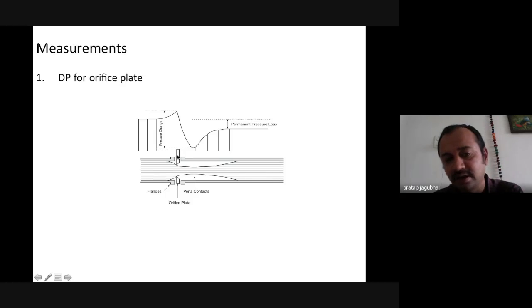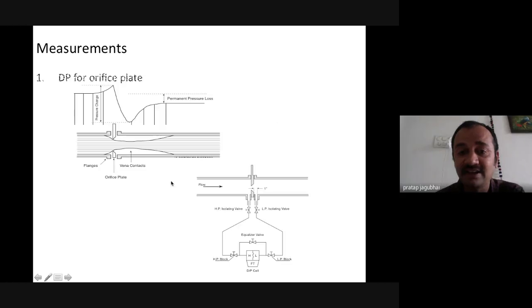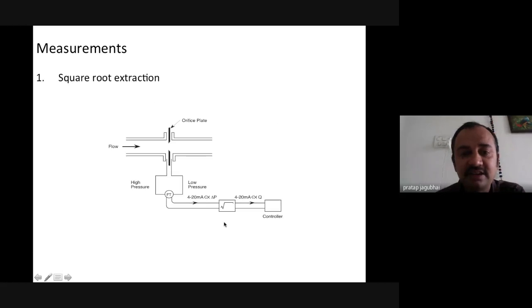In the DP type measurement, the orifice plate is inserted inside the flowing media, where you can see that when the orifice plate is available, there will be a pressure difference, and the lowest point of the pressure, which is getting dropped, is called the vena contracta point, and we take the pressure difference from this point to this point, which is a differential pressure equivalent to the flow. And this is very well defined from Bernoulli's equation, where flow is proportional to the square root of dP. So this dP is taken by the differential pressure transmitter, and again taken to the square root extraction device, which will convert this into 4-20 milliampere, and this 4-20 milliampere will be proportional to the volumetric flow, or in case of mass flow also, with the correction applied with the density and all that.